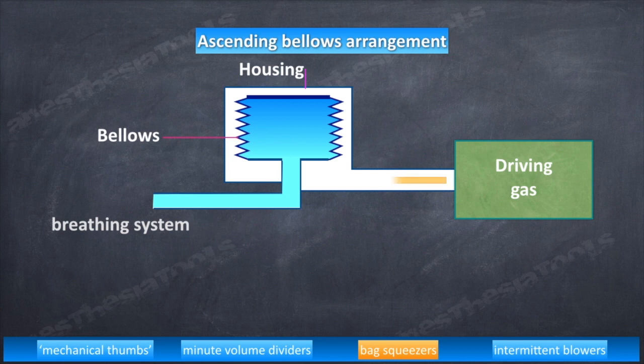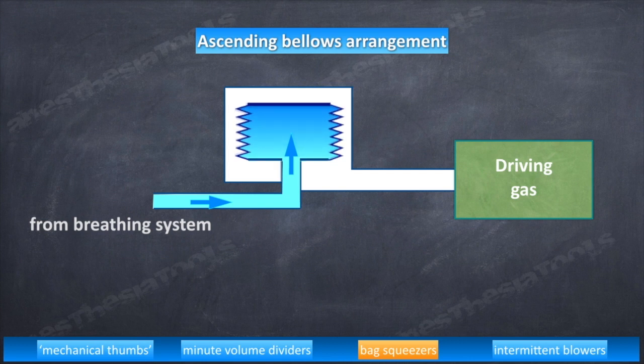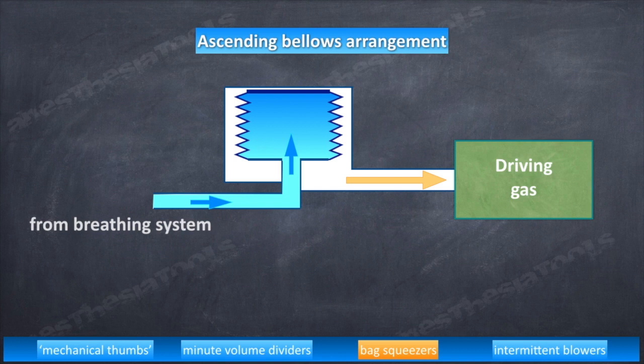Once again, see the drive gas being pushed into the housing. Now the bellows are pushed down, creating gas flow into the breathing system. During exhalation, gas from the breathing system goes into the bellows and the ascending bellows rise. You can see the drive gas escaping through the exhaust valve.